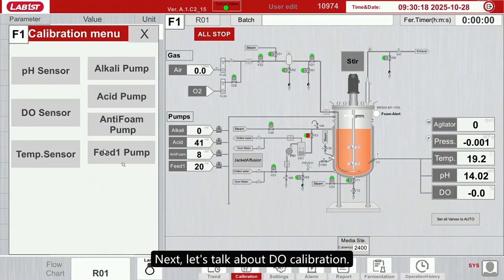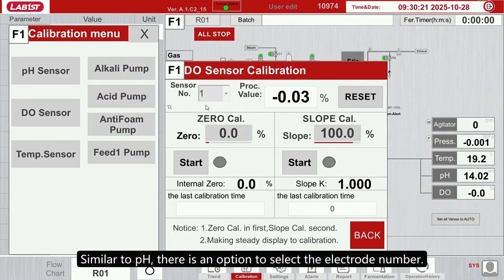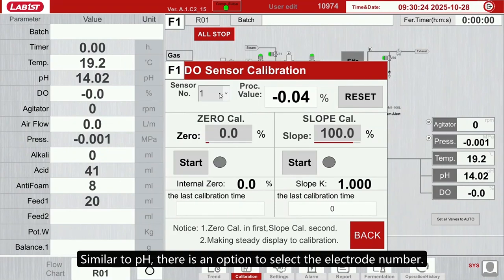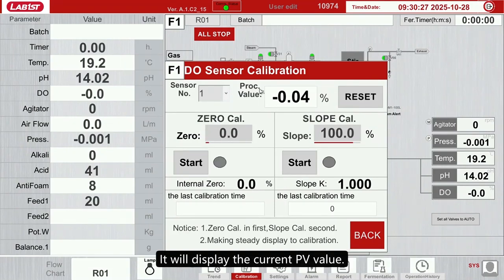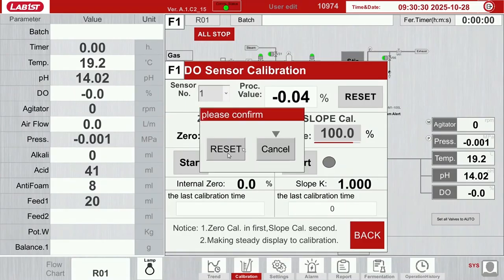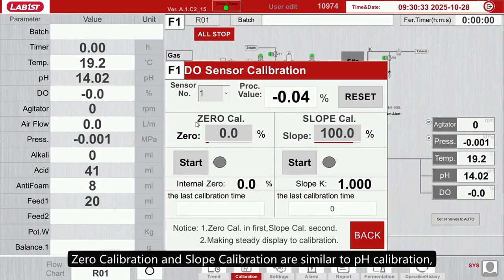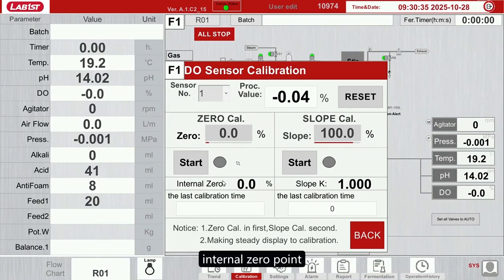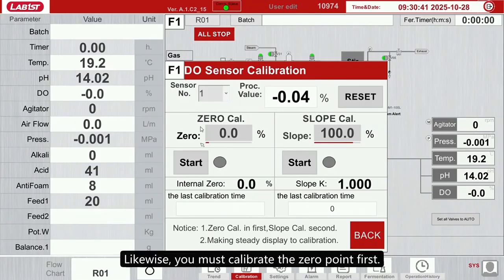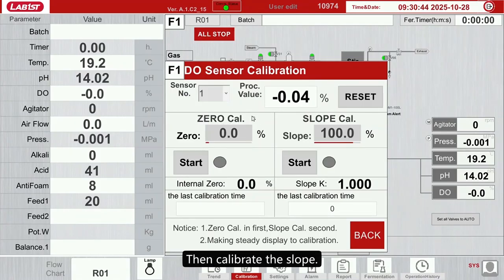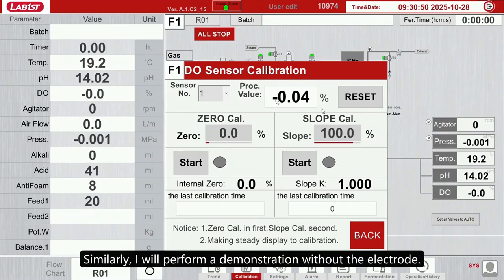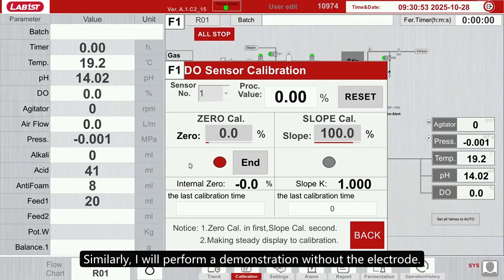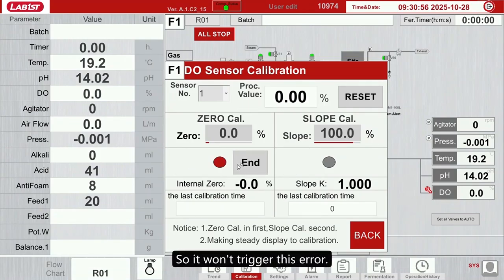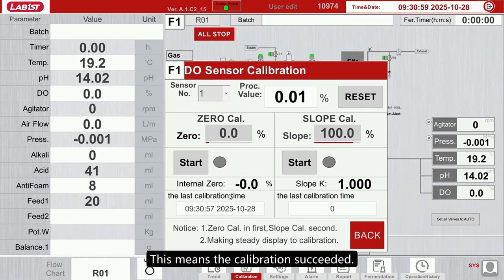Next, let's talk about DO calibration. Similar to pH, there is an option to select the electrode number. It will display the current PV value. There is also a reset function. Zero calibration and slope calibration are similar to pH calibration, with the internal 0 point and calibration procedure. Likewise, you must calibrate the 0 point first, then calibrate the slope. Similarly, I will perform a demonstration without the electrode. Because it's currently 0, it won't trigger this error. This means the calibration succeeded.